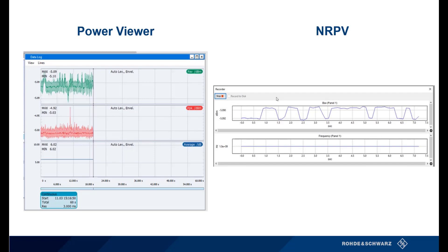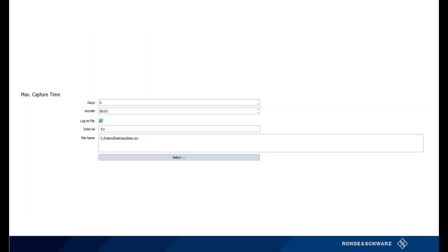One last feature I'm going to highlight is called Data Logger. Data Logging allows the user to record and export the data you collect — such as maximum, minimum, and average values — in ASCII format. Both of these features can be seen in the images. If Data Logging is a feature you require, Power Viewer allows for the most flexibility when setting parameters. Power Viewer allows you to record based on a set interval time for measurements and duration, while NRPV will record until the user stops it. The image on the screen shows where the parameters in Power Viewer are set.